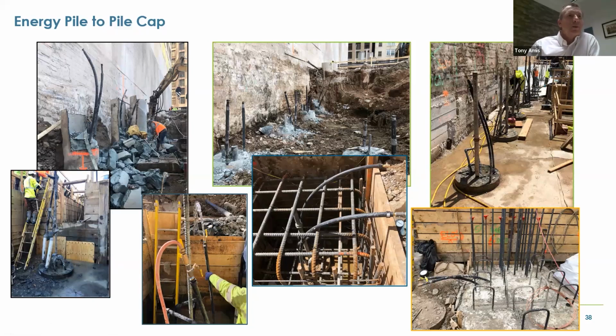That said, that white tubing you can see in this little picture down on the left - as the pile's been excavated, the last thing we want is for the geothermal loops to be damaged in this zone. So we provide this extra protection so we don't damage the loop at this point. If we damage it here, we've got to break out further down the pile, which is always a frustrating job for the guy on the jackhammer.